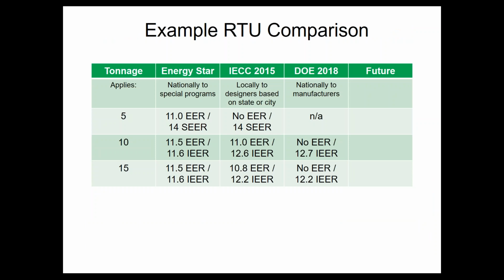If you look at those requirements, the DOE 2018 column next to the 2015 code IECC column, they in fact are very similar. There's a slight difference there. At some sizes, I put 5, 10, and 15 ton examples on here. You can see the 10 ton, I need to get a 12.7 IEER unit instead of a 12.6. But the purpose of showing it to you this way is that if you get a DOE 2018 compliant unit, you're pretty much going to automatically comply with the state. However, if you buy an Energy Star compliant unit, which you would think would be the best stuff out there, you will not comply with either one of these things, right? So the Energy Star spec is fairly outdated, and they're probably going to update that soon, I would think.